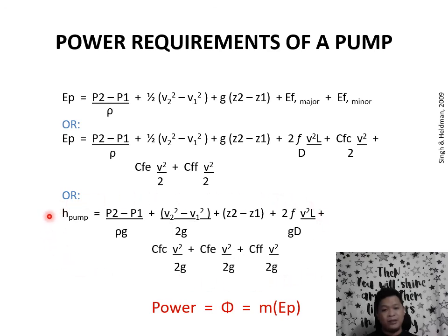There's also this format, yung head format na tinatawag natin. Notice meron siyang G sa ilalim, yung gravitational constant, which naman converts the final units to just the length dimension, puro meters. No, kasi yung pump head na pag-uusapan natin later on, yun naman ay nakabase sa yung simplification na parang gaano kataas ang katumbas nito na itong energy na to, gaano kataas na height ang kaya niyang iangat yung fluid, parang ganon. Yun kasi yung pump head terminologies.